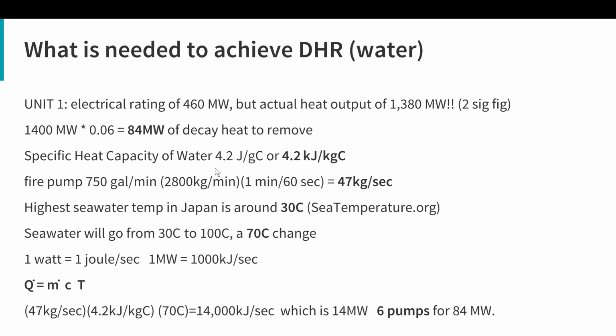The specific heat capacity of the water is 4.2 joules per gram Celsius, or since we're going to be using kilojoules, 4.2 kilojoules per kilogram. And the fire pump for our system, we were hoping that we could just roll up a fire truck and have that go to the secondary side of the condenser or cooling tower or whatever we're going to use. And that's going to pump 750 gallons a minute, which is the same thing as 2,800 kilograms per minute, or 47 kilograms per second. And we're going to use the seawater temperature. The highest one I found was 25, 26 degrees. We're going to go ahead and use 30 degrees. This is from seatemperatures.org. We're going to use 30 degrees Celsius as a conservative seawater inlet temperature.